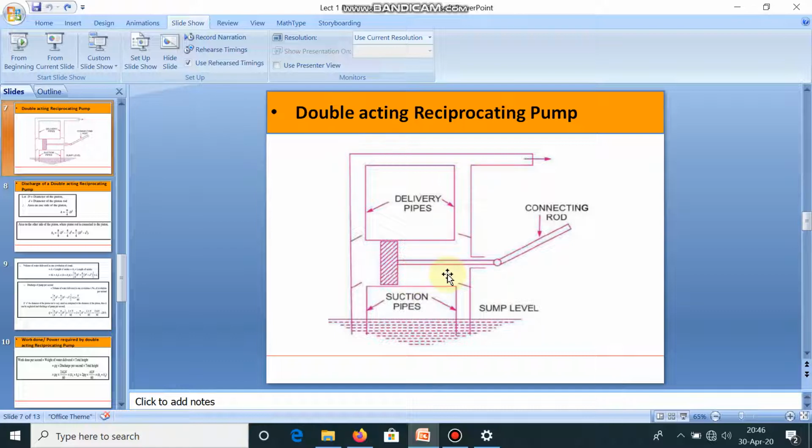When the piston moves towards the left, at the back side of the piston the volume of working medium increases, that drops the pressure below atmospheric pressure. That's why the suction valve in suction pipe number 2 gets open and liquid from the sump is sucked in at the back side of the piston.